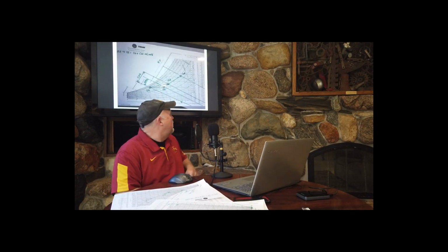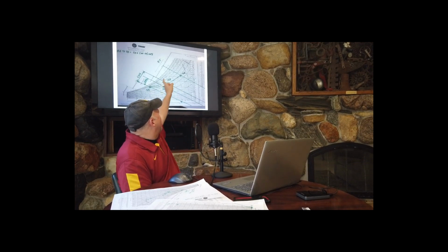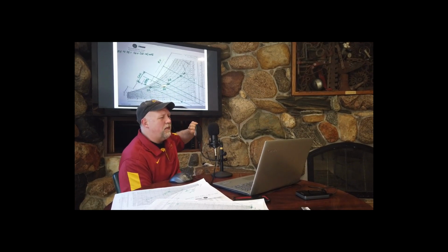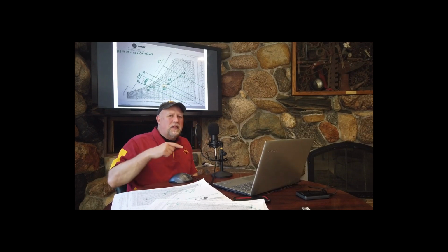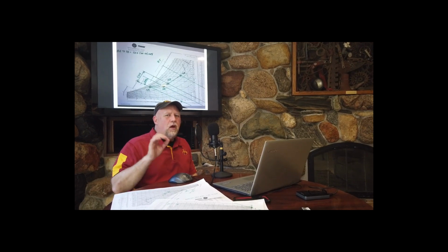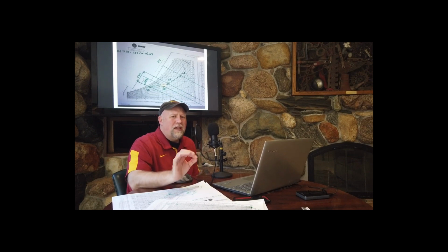All right, and then I did something that I didn't do in yesterday's examples. What I did is I plotted it as if this was an entire psychrometric loop. The term is a psychrometric loop. A loop, something that is going to repeat again and again and again. Remember, the whole point of HVAC system and our calculations is to bring the building into an equilibrium. An equilibrium is achieved when our space temperature stays the same. It's not getting hotter and it's not cooling down.